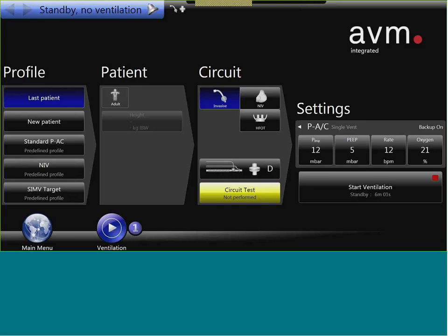For non-invasive, invasive, many ventilators have one non-invasive mode. So it's easy to switch to just that non-invasive mode. But as long as we are offering all ventilation modes, or nearly all pressure controlled modes for non-invasive as well, I think this would lead to confusion, because then we would have a very long panel with non-invasive, invasive modes, and sometimes people wouldn't know the difference anymore.